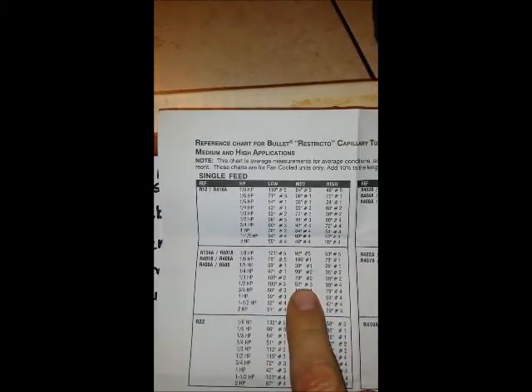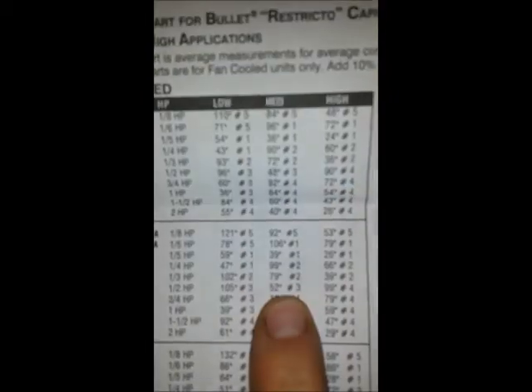So that's going to be right here, medium temp, because it's a cooler. And we're going to find half horse right here. So the capillary tube has to be 52 inches long and number three.